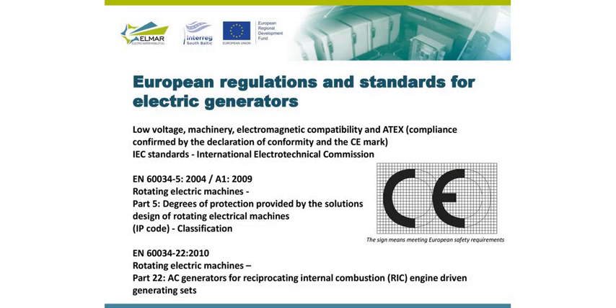There are regulations for electric generators. The low voltage, machinery, electromagnetic compatibility, and ATEX directives allow the use of the CE mark, and there are IEC standards which also need to be met for rotating electrical machines. We need to also take care of the IP code, especially important for marine applications. Another standard for rotating machines is for AC generators driven by reciprocating internal combustion engines, generating sets. So this is the specified standard for the discussed generators.